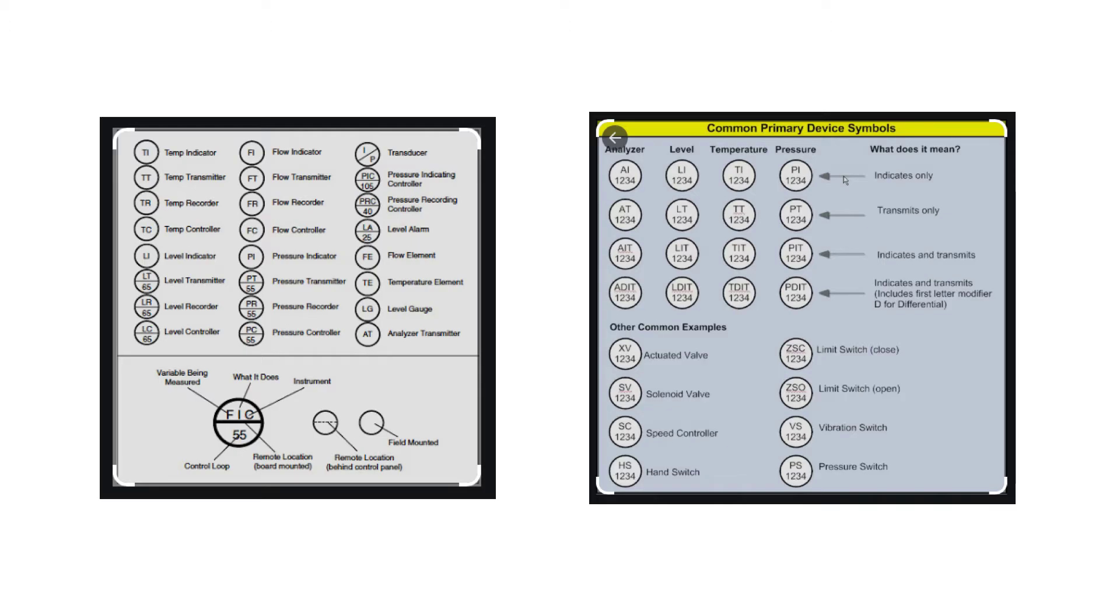So the first letter on the tag is a variable being measured. So whether that's flow, pressure, temperature. What it does - does it indicate, does it record, does it transmit? And then you also have what type of instrument it is: a control valve, a gauge, an alarm, a transducer, a transmitter, etc.